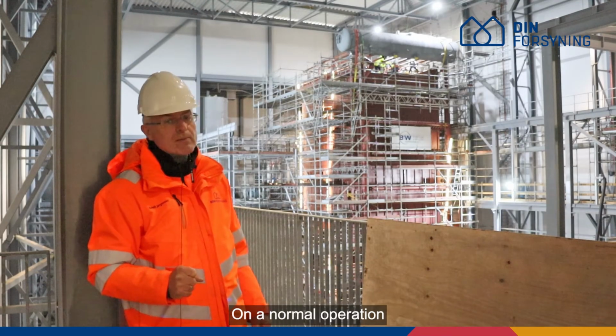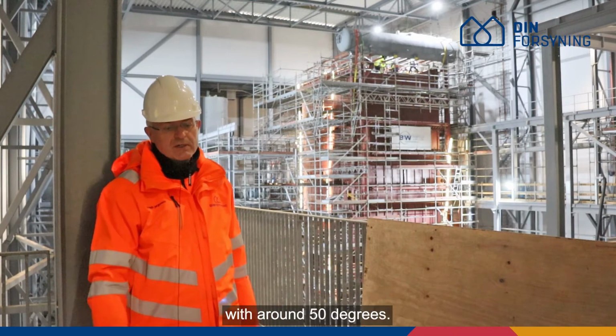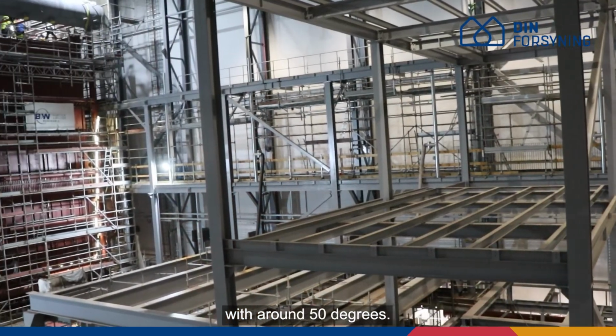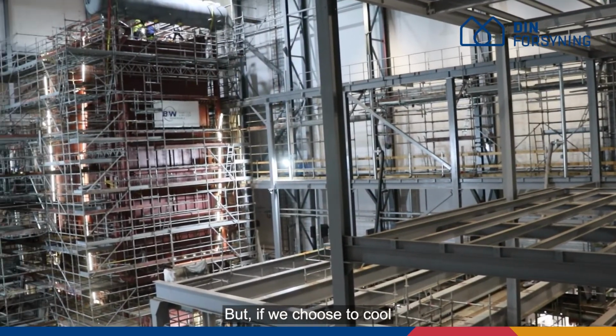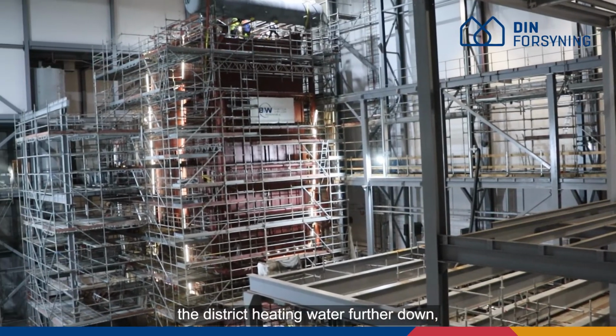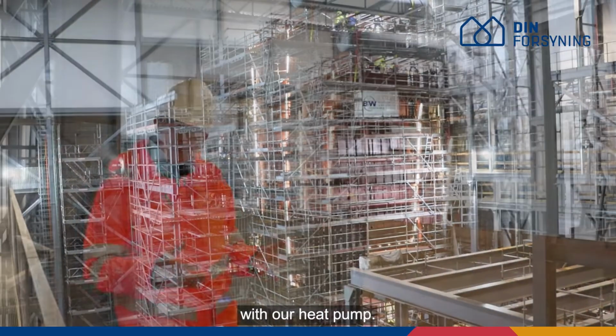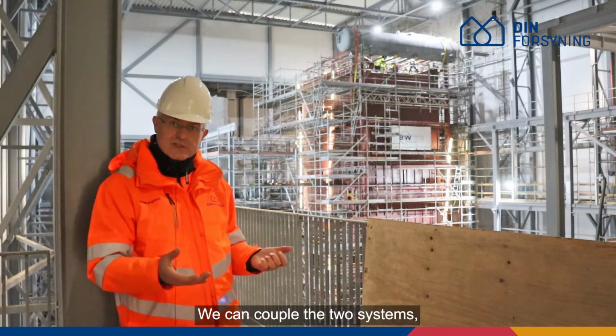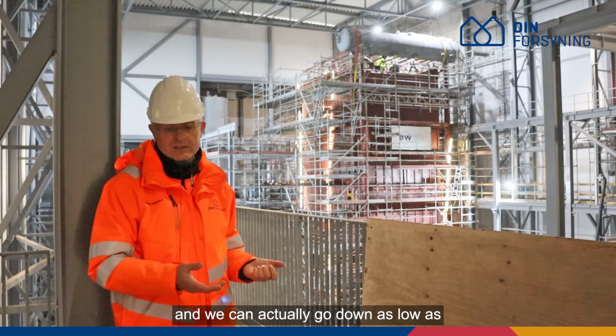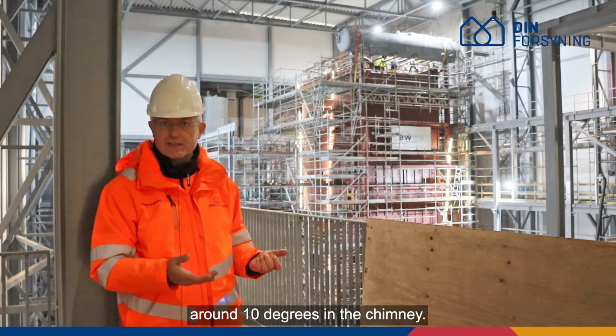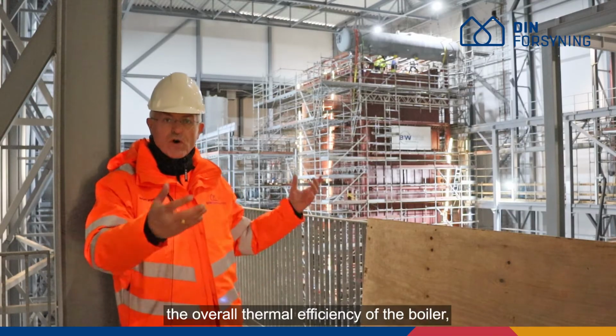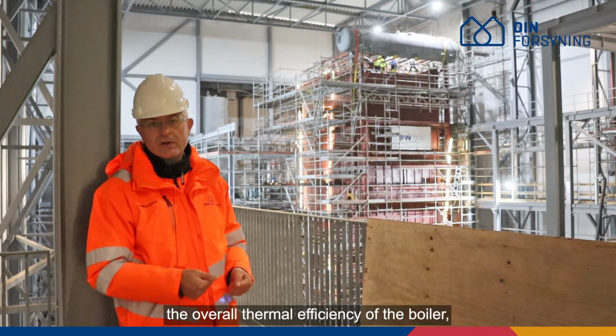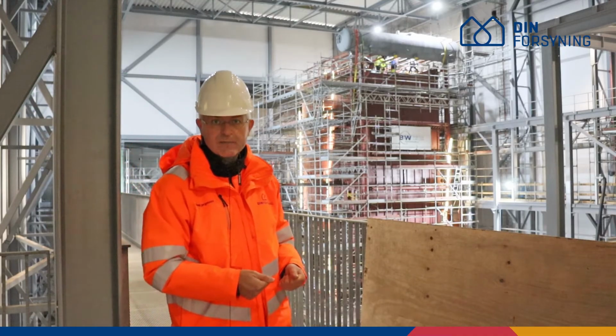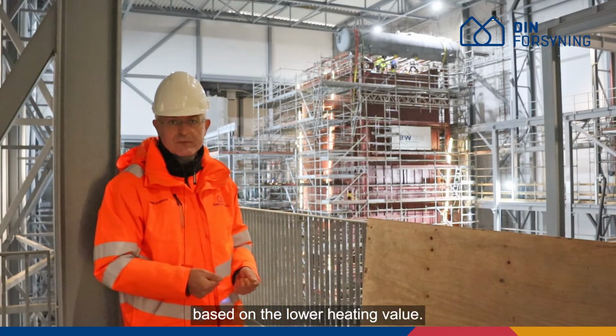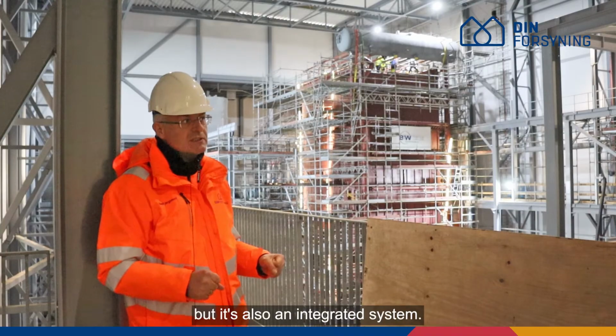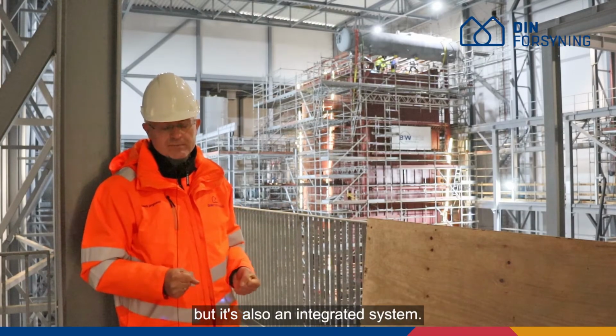On normal operation, we will enter the chimney with around 50 degrees. But if we choose to cool the district heating water further down with our heat pump, we can couple the two systems and we can actually go down as low as around 10 degrees in the chimney, which means that the overall thermal efficiency of the boiler exceeds 120% based on the lower heating value. So it's a good system, but it's also an integrated system.